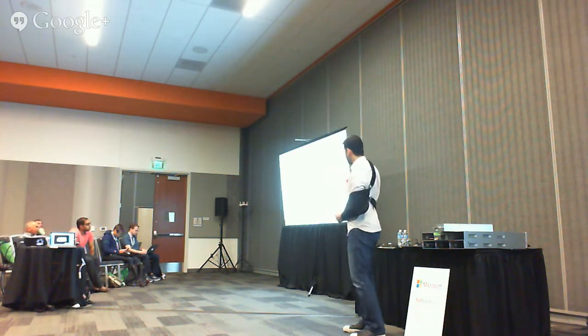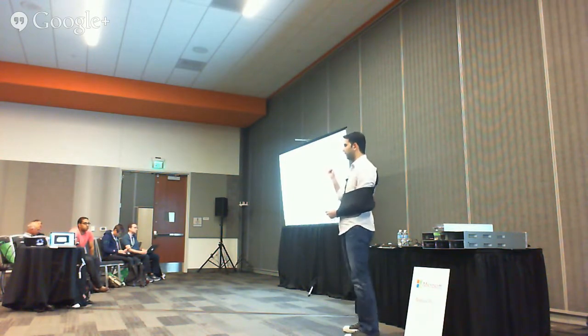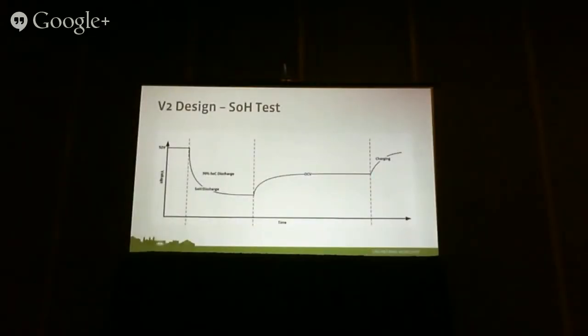What's interesting about our SOH test: when we started looking into how to do battery tests a couple of years ago, everybody in the industry was discharging their battery fully, up to 80 to 90% discharge, then letting it sit for OCV time—open circuit voltage time—and from there determining how much the internal impedance had increased compared to the previous test, and how long it takes to stabilize. Then you can do capacity and impedance calculations.